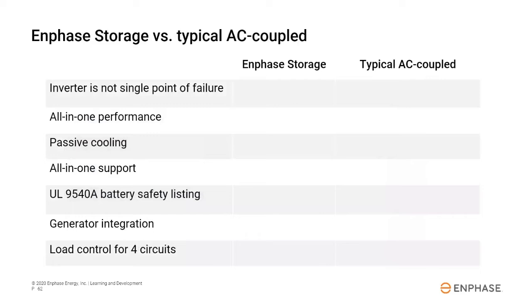So let's review a summary of the key differences between Enphase storage and typical AC coupled. First, multiple microinverters provide redundancy and eliminate the inverter as a single point of failure. Enphase storage can fine-tune the solar output so solar always stays on and the battery stays fully charged. The passive cooling system eliminates more fail points and operates silently. All-in-one support from Enphase storage, so you're going to have all-in-one support and warranty from Enphase. The UL 9540A listing for safety, which Enphase has and nobody else has.